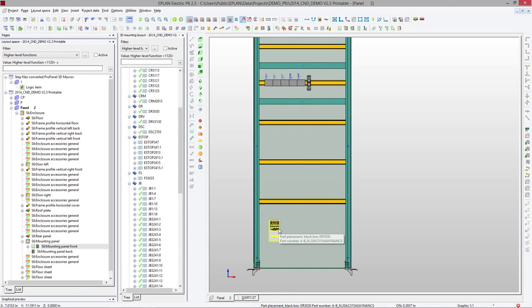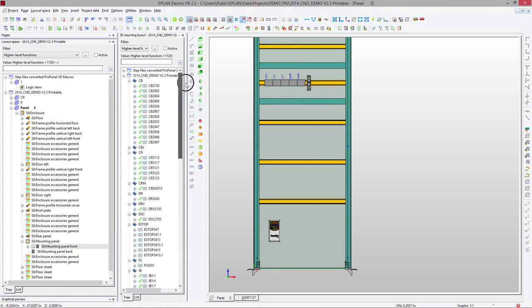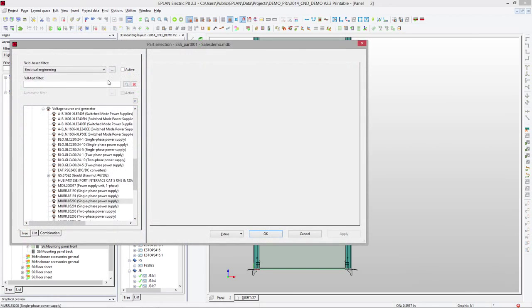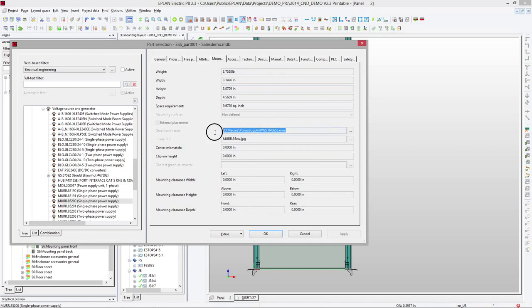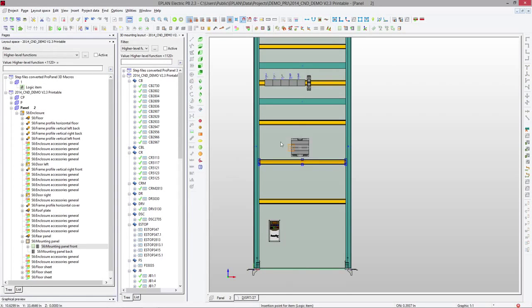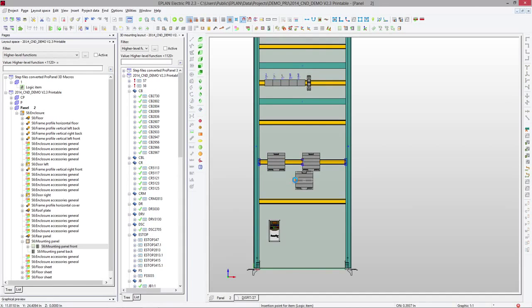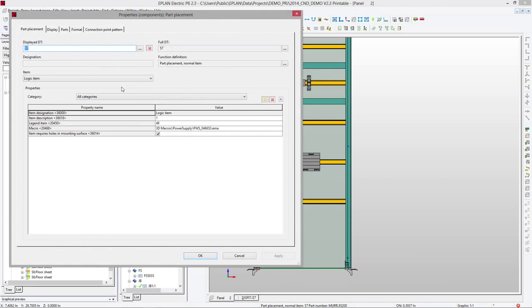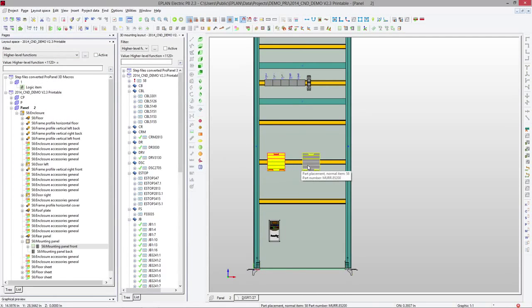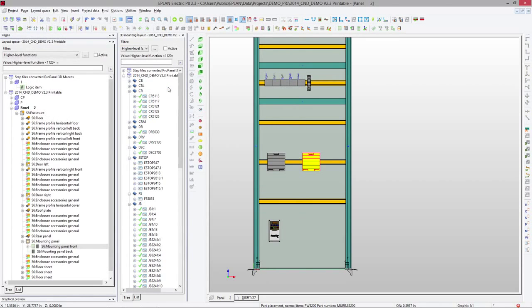Now, from this point on, you can also place components that are not yet in the schematics, because these components, they were existing in the schematics, you can insert devices. So if you remember earlier, we had placed and created a macro, which we assigned here to this part number. Now, when I'm placing the device here, it's actually asking me for this device. This macro is pulled in. I can even give it a name. I can actually give it a device tag. Now, this device tag will be reflected anywhere in ePlan, in the device list, or anywhere else where you actually go.